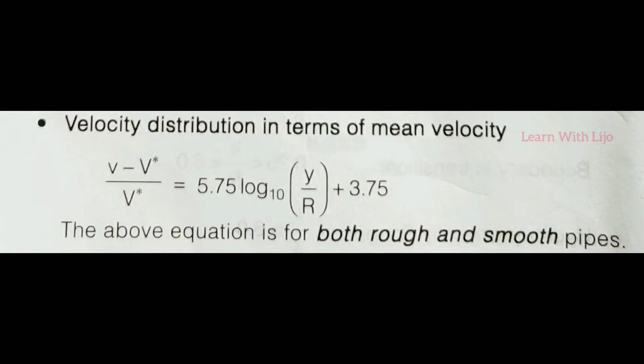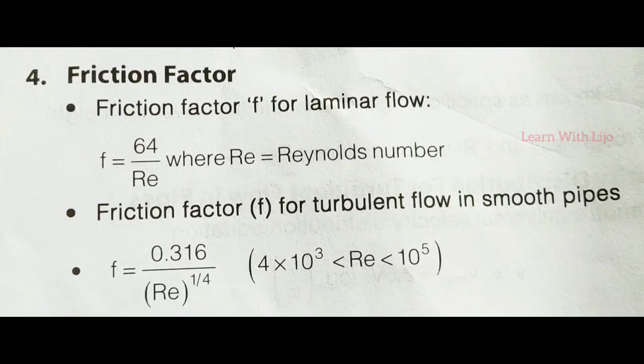Friction factor f for turbulent flow in smooth pipe is f equal to 0.316 by Re raised to 1 by 4, where Re is between 4 into 10 raised to 3 and 10 raised to 5. Then 1 by root of f is equal to 2 log 10 of Re into root of f minus 0.8. Friction factor f for turbulent flow in rough pipe: 1 by root of f equal to 2 log 10 R by K plus 1.74. The equation shows that for rough pipe, friction factor depends on R by K, not on Reynolds number.